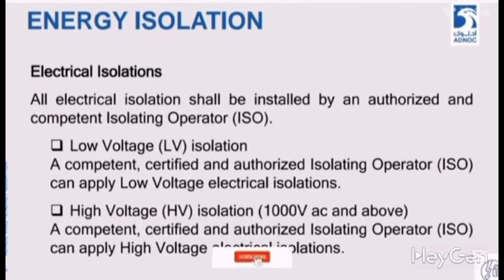Electric isolation. To electrically isolate any equipment, component or machine, the ISO Isolation Authority, which is a technician from the electrical department, will come and be authorized to isolate it upon the recommendation of the ISA Isolation Authority, who will be the electrical supervisor in electric isolation.